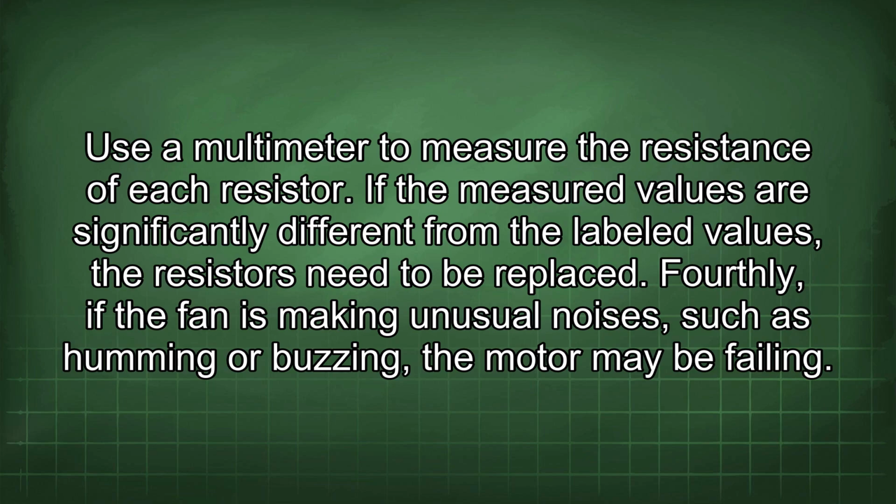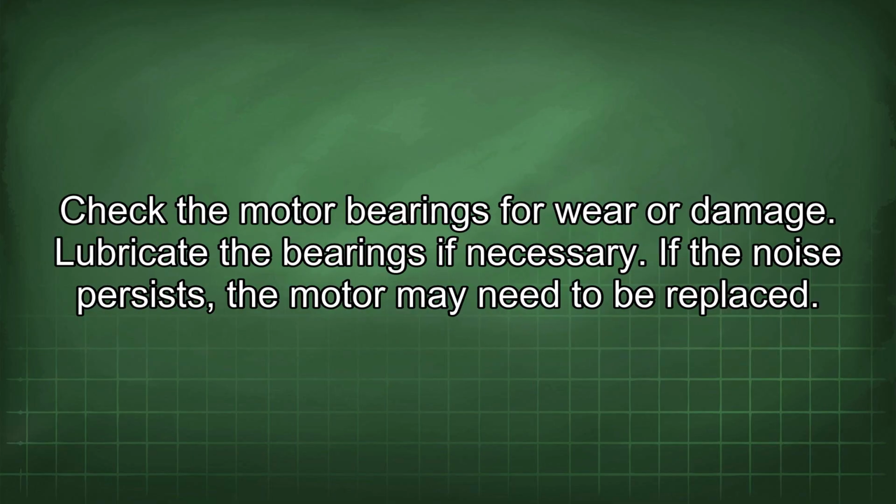Fourthly, if the fan is making unusual noises, such as humming or buzzing, the motor may be failing. Check the motor bearings for wear or damage. Lubricate the bearings if necessary. If the noise persists, the motor may need to be replaced.